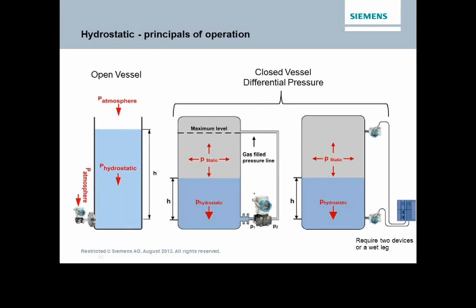So I can do that with either a single transmitter and a wet leg, or I can do 2 separate transmitters, and then I have all the issues of zeroing out the transmitters, taking into account things like the fill fluid, the density of that fill fluid, and height. So zeroing out the transmitter and making adjustments for this becomes important. If I have a process that I need to make sure doesn't block, I need to put seals on these, so it gets a little bit more complicated. So some of the principles that we're talking about here are still making a measurement. The main thing, again, is I want to know what's in that tank and the level in that tank. So different technologies have been used in the past to make that measurement.